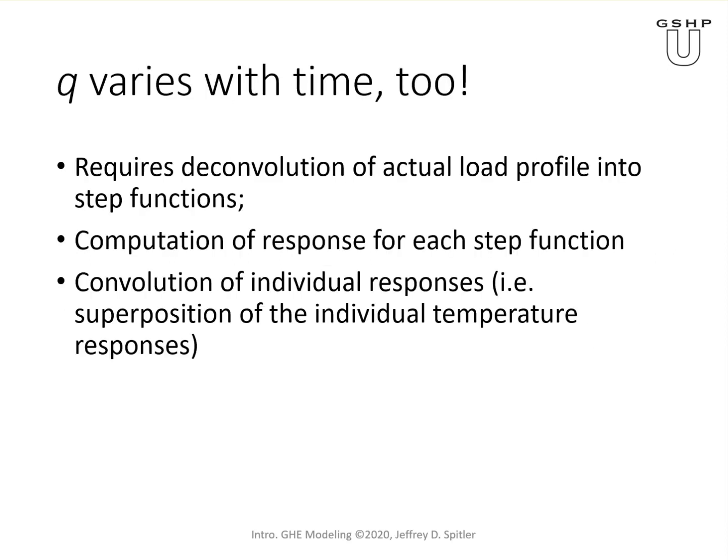In practice, Q also varies with time. The way we handle this is to deconvolve the actual load profile into a series of step functions, compute the response for each step function, and then superimpose — convolute — the individual temperature responses. This procedure was originally developed by Professor Clausen and his graduate students, and we still use it today.